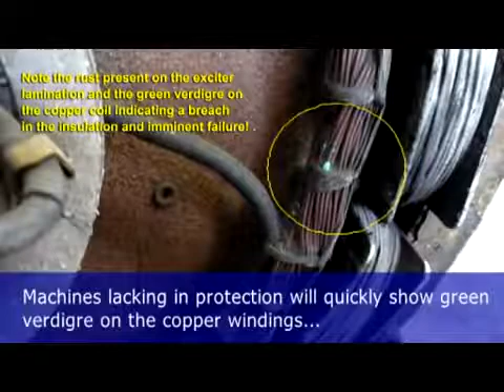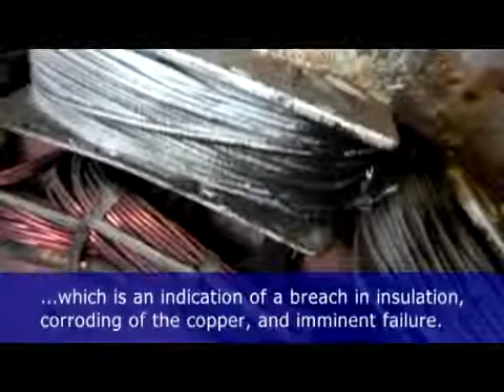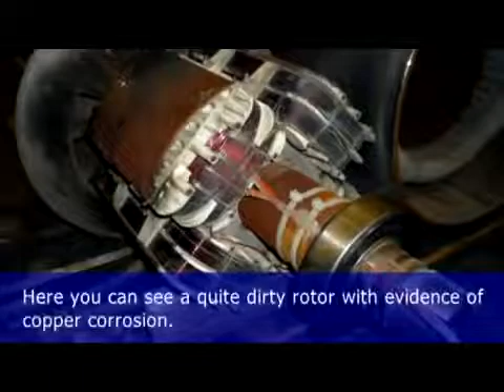Machines lacking in protection will quickly show green verdigris on the copper windings, which is an indication of a breach of the insulation, corroding of the copper and imminent failure. Here you can see a quite dirty rotor with evidence of copper corrosion. Damp air, high humidity or condensation will reduce the effectiveness of the insulation system within the alternator. A weak insulation system will allow voltage to pass phase to phase, phase to neutral or phase to auxiliary winding. In any event, it is a total failure of the winding.